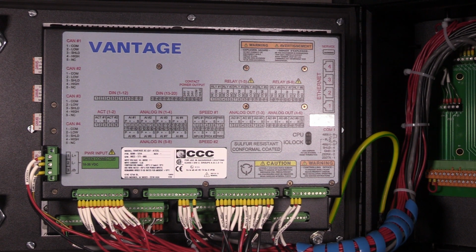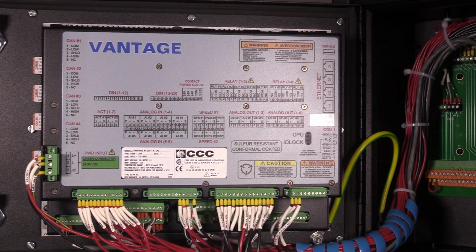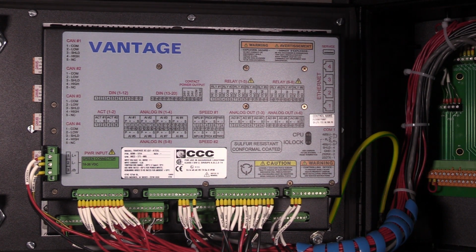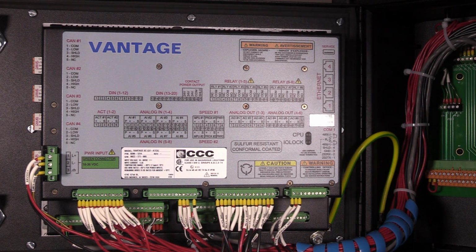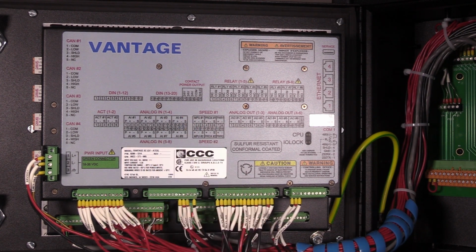If desired, an external 16 to 32 volt DC power source can be used for the circuit wetting voltage. In this case, terminal 24, contact input common, must be connected to the external power source's common to establish a common reference point. Discrete signals only require a single 16 gauge wire. Wire the discrete signal connection from the end device to a numbered digital input terminal labeled DIN on the controller. The numbered terminal the signal was wired to will correspond to the numbered channel in the controller.